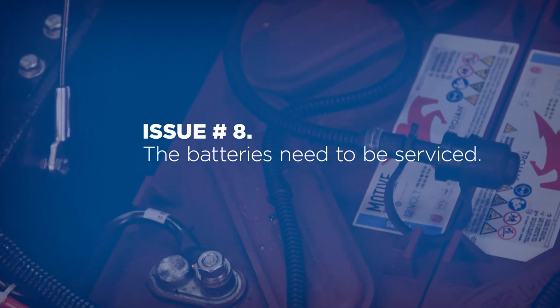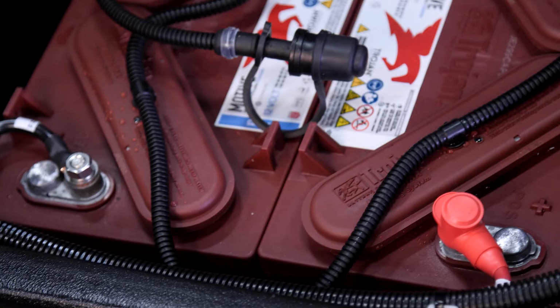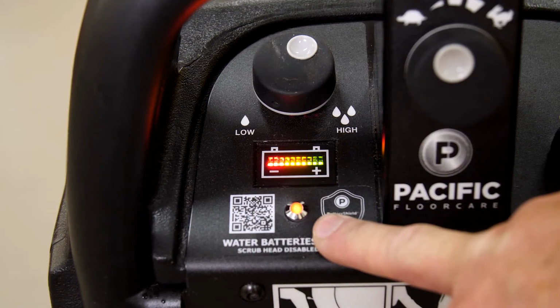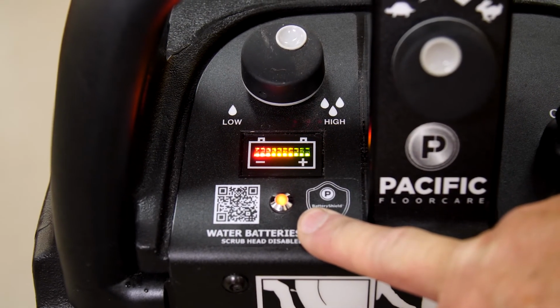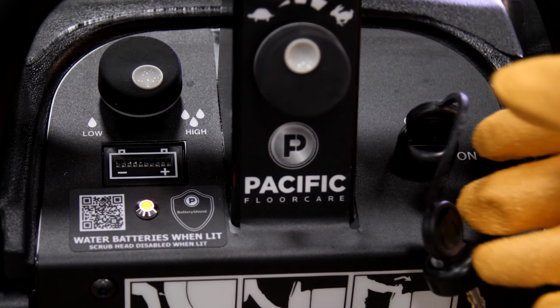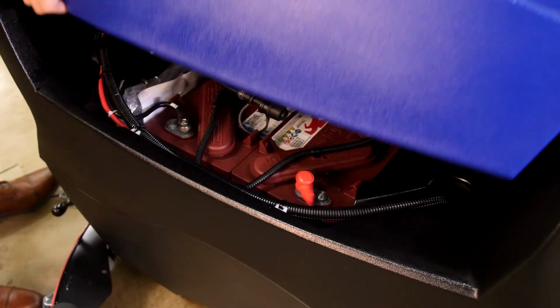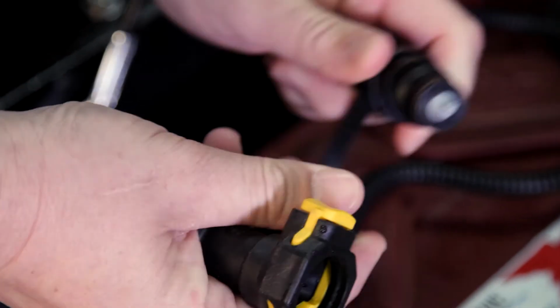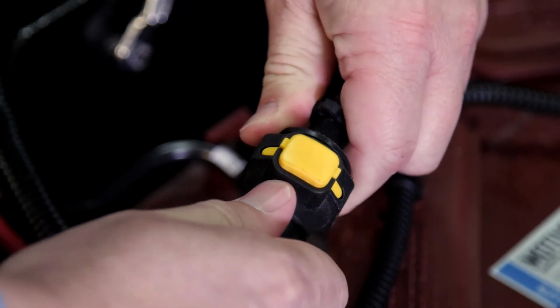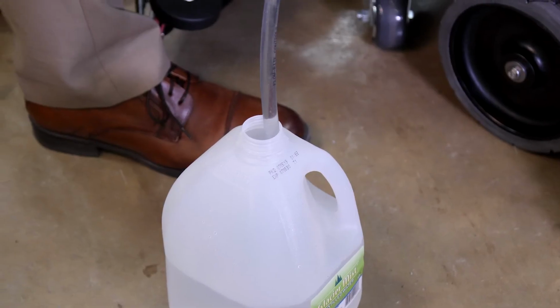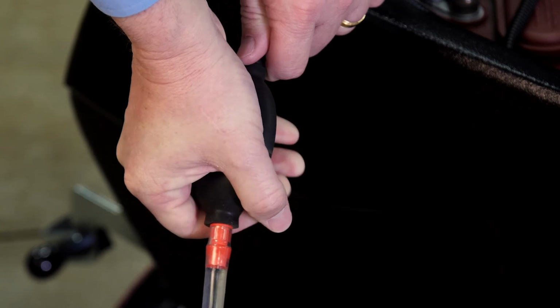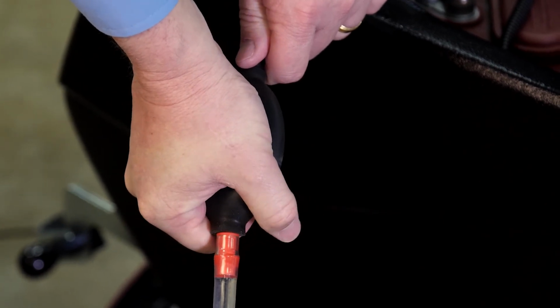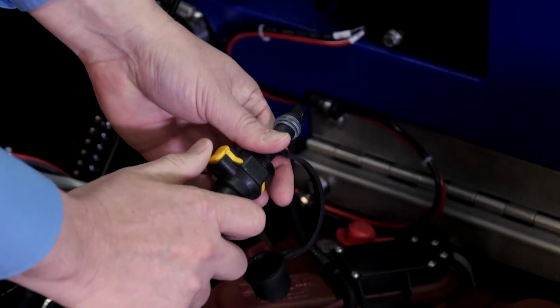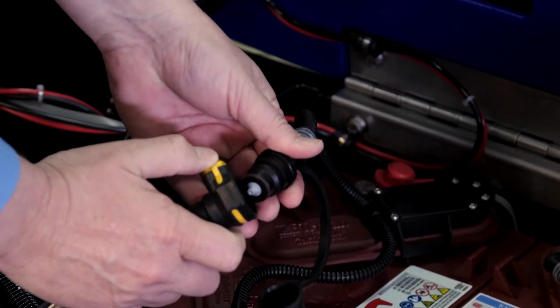Issue number 8. The batteries need to be serviced. In this case, the user will be notified by the battery shield warning light on the control panel. When this light is triggered, it is time to water the batteries. Open the tank exposing the batteries. Find the water system hose end and remove the protective cap. Hook the provided pump hose to the battery's water hose via the quick release end. Put the other end in your source water. Squeeze the hose pump ball until it is firm. At this point, the batteries are full. Detach the pump hose and replace the protective cap.